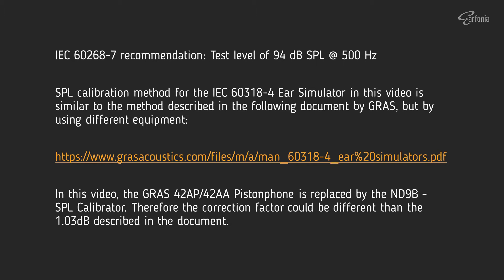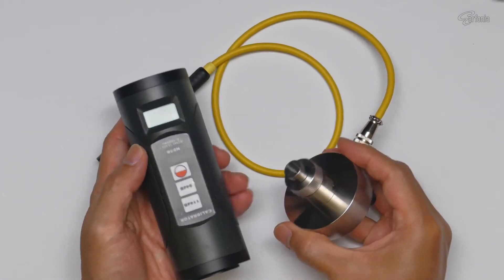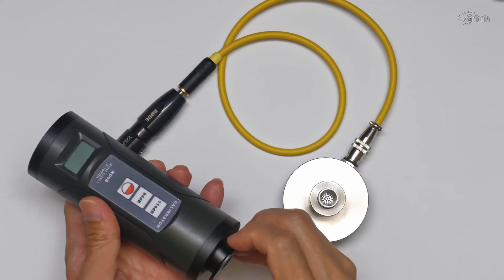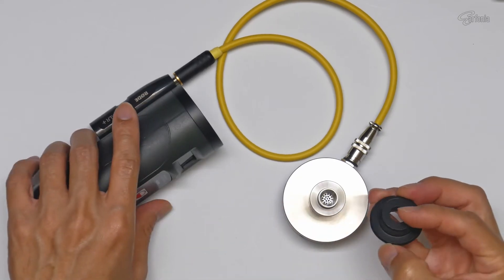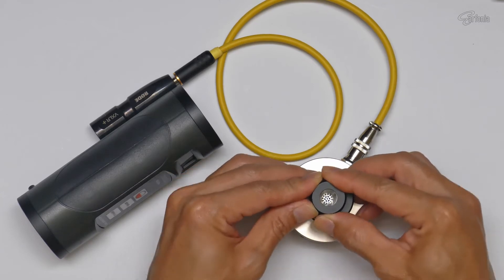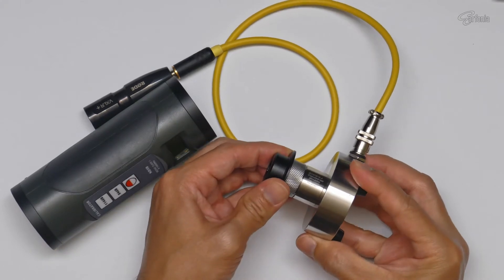The calibration method in this video is similar to the level calibration procedure described in a document from GRAS. But I will be using different equipment — instead of the GRAS 42AP or 42AA pistonphone, I will be using the ND9B SPL calibrator, and then coupling it to the IEC711 coupler.